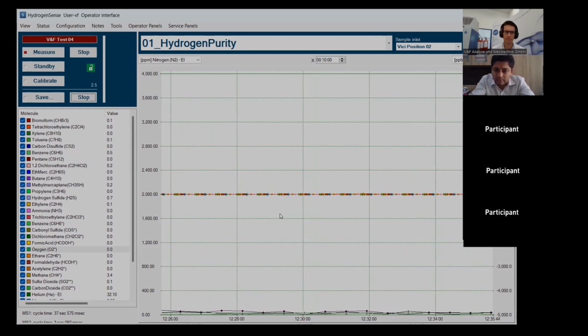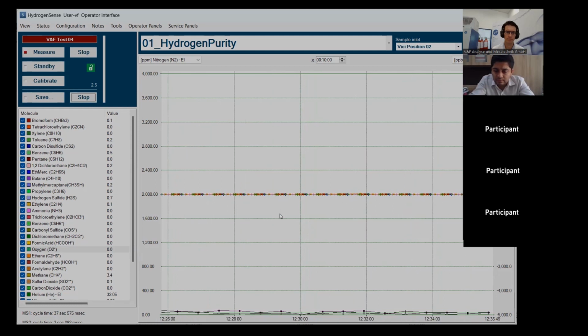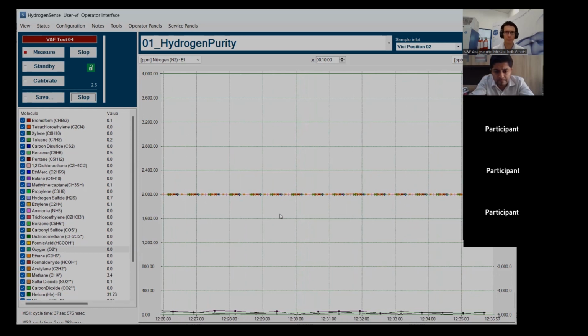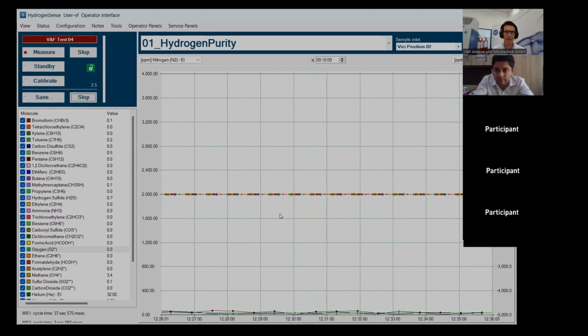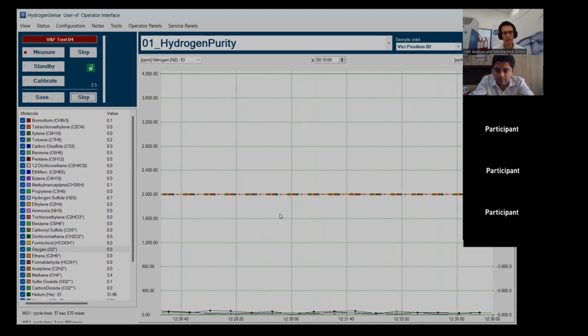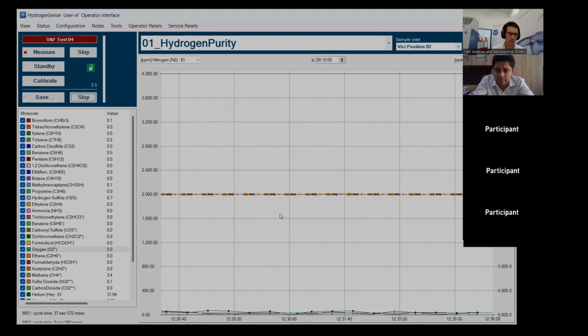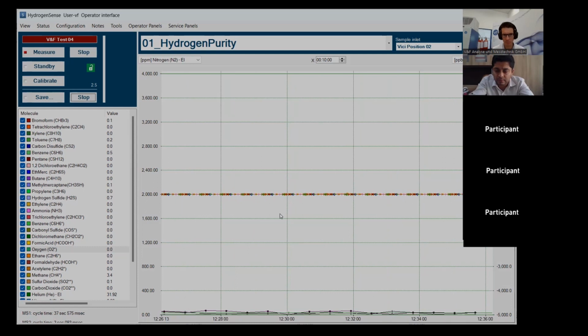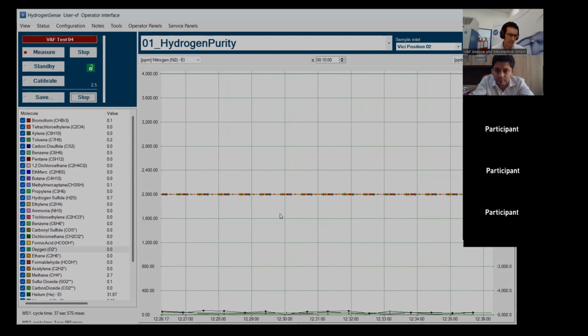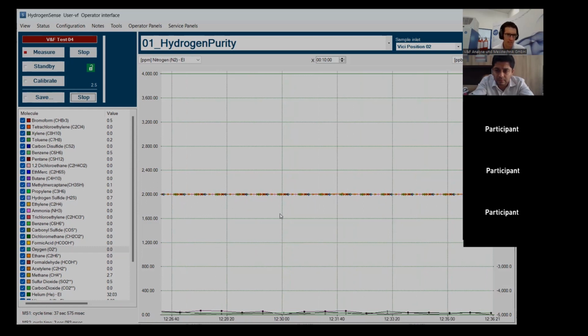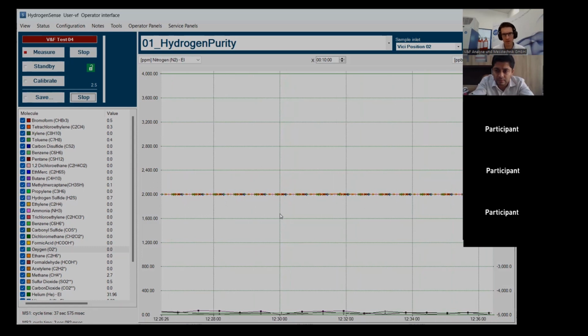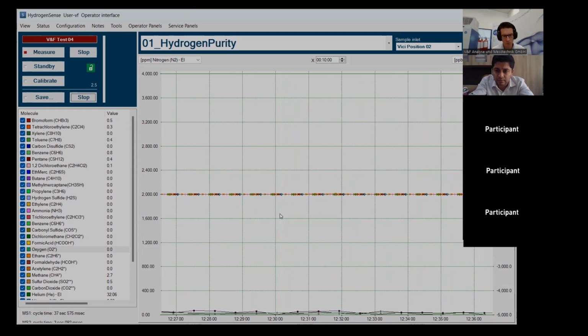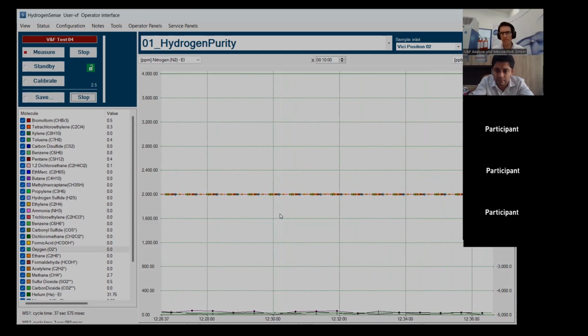And you mentioned that even if we are not analyzing, it would still need some hydrogen running through the system. So basically, a hydrogen cylinder is required, which would always be giving some hydrogen in case the plant hydrogen is not available. Exactly. That is the most stable way to operate the instrument. This is going rather deep into the technicals, but you can run the instrument on pretty much any gas. There is a certain chemistry on the ion source parts once you apply hydrogen. Hydrogen has very high reductive properties, and ambient air has oxidative properties on the filament material, meaning that when you switch between the two, there is a certain stabilization time until the instrument is completely saturated in the new gas. That is why we typically recommend having the hydrogen running.